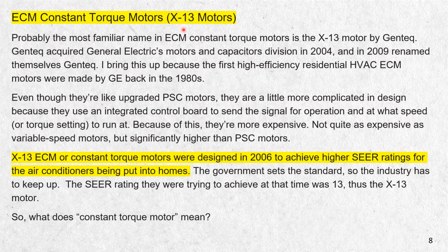Now, some of you that do know this part could probably fast forward a couple more slides. We're going to talk about what is a constant torque motor. For those that don't know, where was the X13 and where did it come from? Well, General Electric is the one that came out with your first PSC motors back in the 80s. Some furnaces that are 30 years old will have that PSC, and it was a high, medium, low 3-speed motor. And in its day, in its time, it was considered very efficient. Well, in 2004, Genteq acquired. So the X13 was designed in 2006 to achieve a higher SEER rating. At the time it was 13 SEER. And so that's why we've come up with the X13.